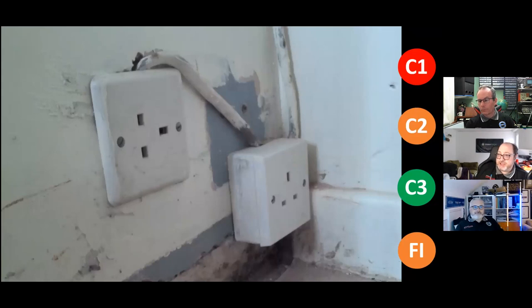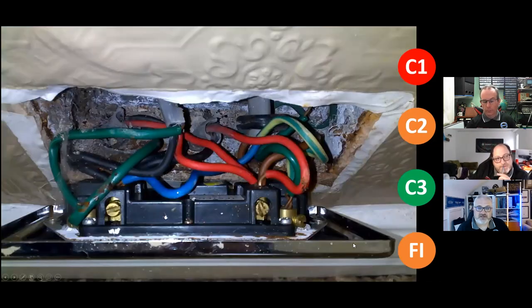location, risk of impact, utilization, maybe. That might push it to a C2. A lot of domestic homes are used as nurseries now. A lot of them are converted, aren't they? They're downstairs nurseries. It's an up and coming business model, it would appear. Right, okay. We'll leave that as a C3. I agree. I think it's a C3 with a little bit more investigation needed. Definitely.